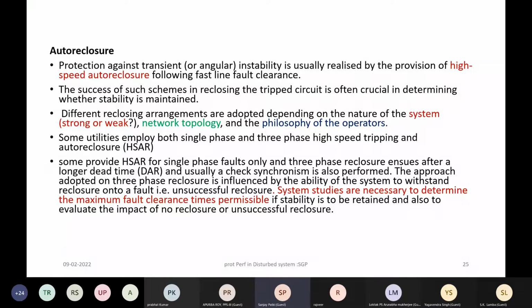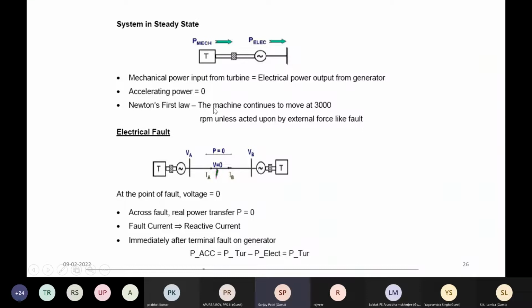Auto reclosure as a measure for maintaining transient stability we had discussed briefly yesterday also. Basically, if you see an electrical fault, we had this 2 machine model of the power system where there is machine 1 and machine 2, and an interconnecting transmission network, which is represented by transmission line X and R. When the fault takes place, immediately after the fault, the difference between the turbine power, the mechanical prime mover power, and the electrical power should be minimized. And this can be minimized by ensuring that the electrical active power component doesn't come down drastically.